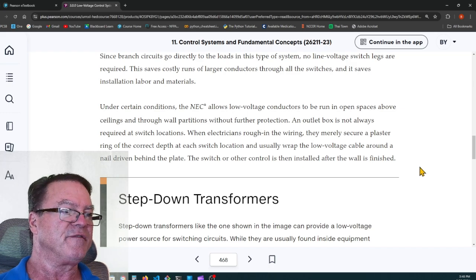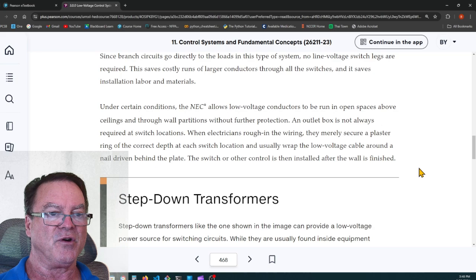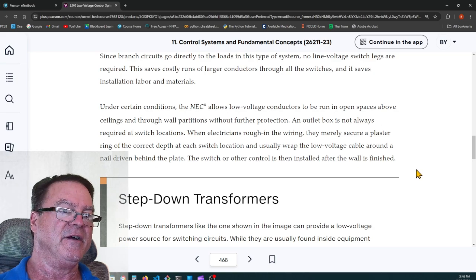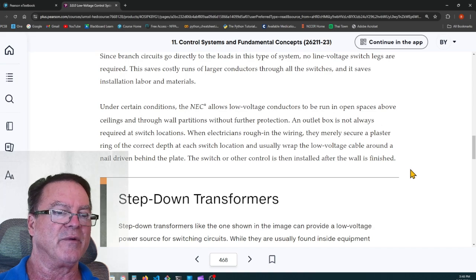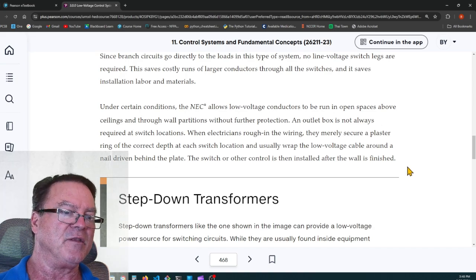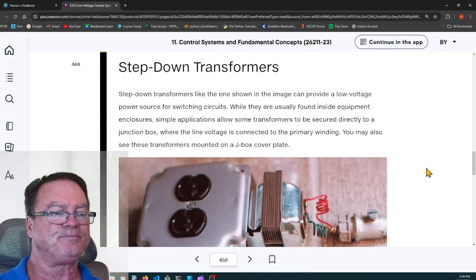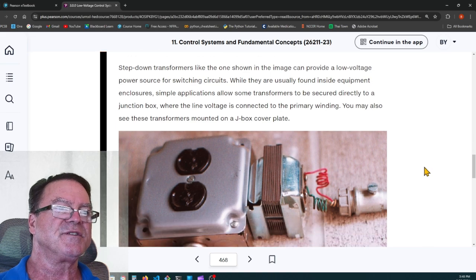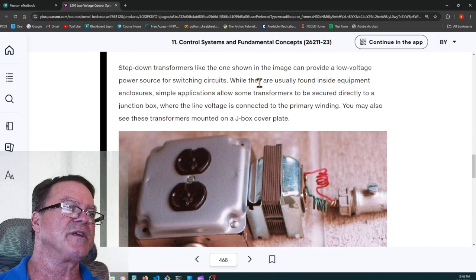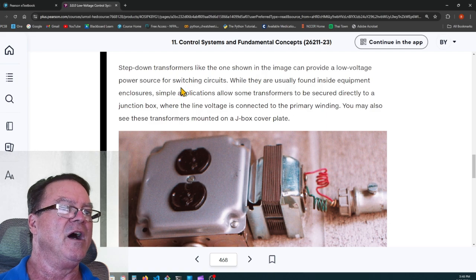When electricians rough in the wiring, they merely secure a plaster ring to the correct depth at each switch location and usually wrap the low voltage cable around the nail driven behind the plate. Switch or other control is then installed after the wall is finished. So here's a step-down transformer. Step-down transformers like the one shown in the image can provide a low voltage power source for switching circuits.